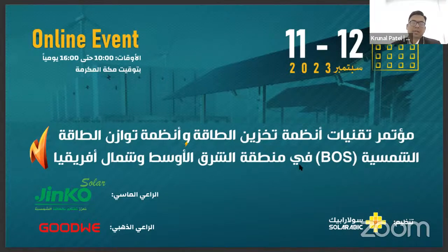Yes, so nowadays we have also observed there are a couple of OEMs that have developed PV plus BESS with the black start feature. Generally, the black start requirement means you have to keep around 30% SOC remaining inside the battery storage, which is specifically used in the case of black start. So if there is no power available, that 30% of SOC will be helpful to generate power for all the controllers, and from there the battery starts working, dispatching power to the grid in the microgrid.